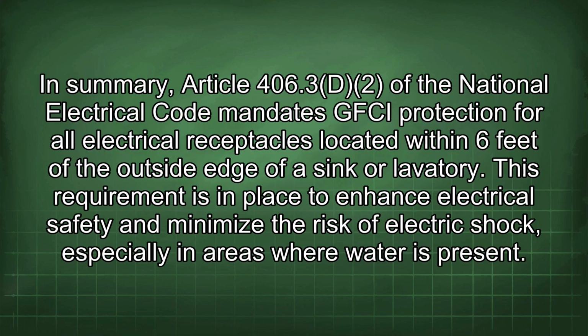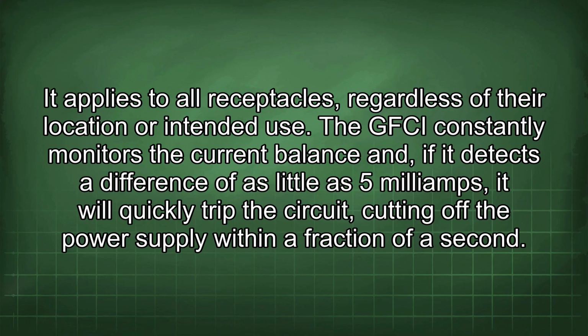In summary, Article 406.3(D)(2) of the National Electrical Code mandates GFCI protection for all electrical receptacles located within 6 feet of the outside edge of a sink or lavatory. This requirement is in place to enhance electrical safety and minimize the risk of electric shock, especially in areas where water is present. It applies to all receptacles, regardless of their location or intended use.